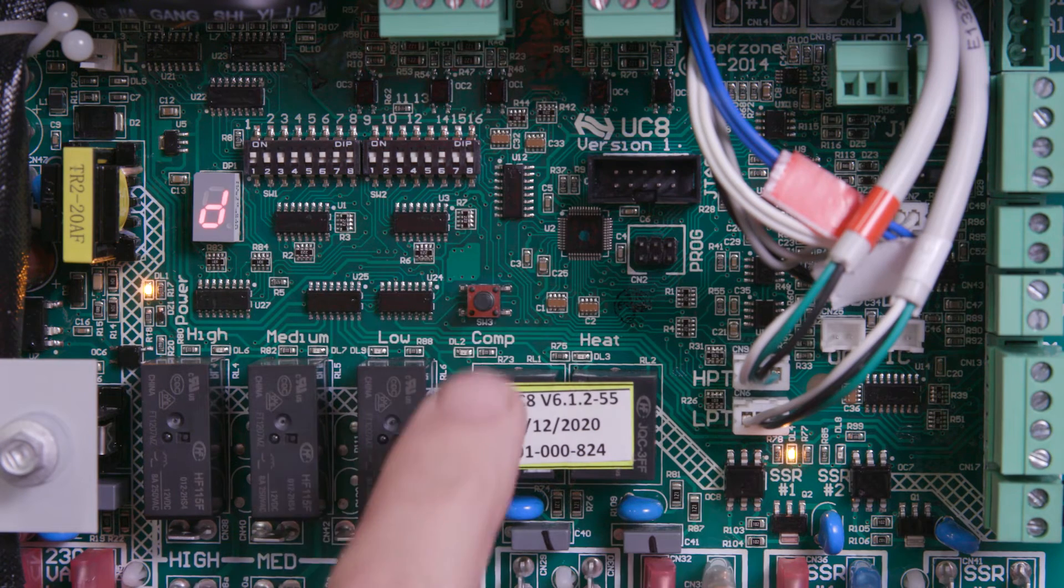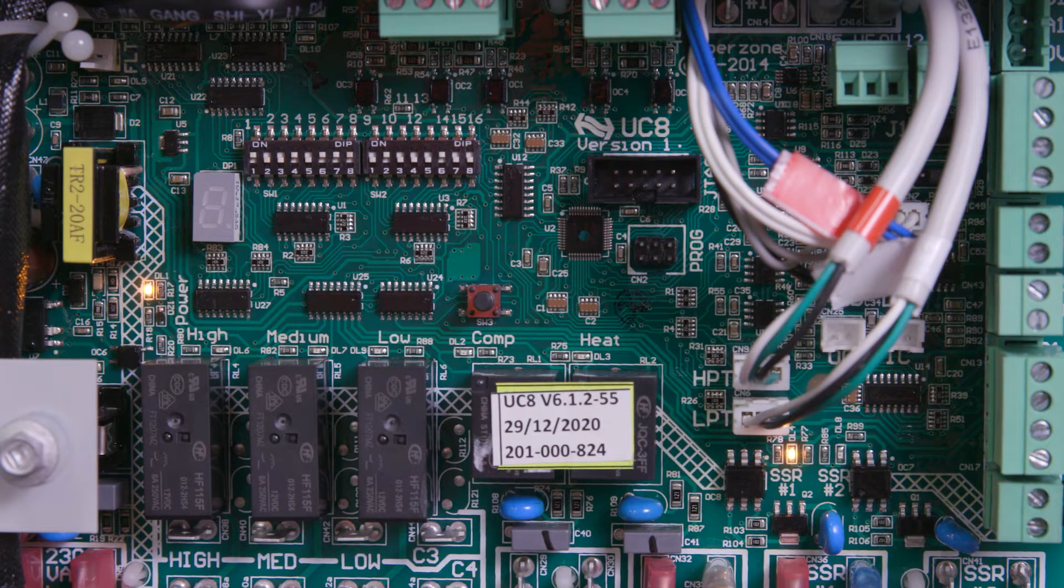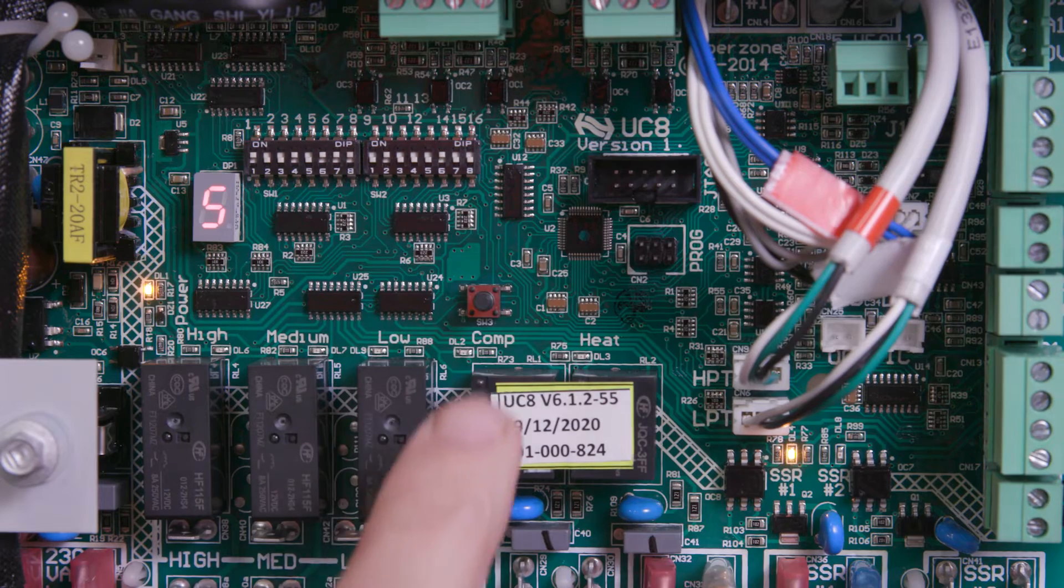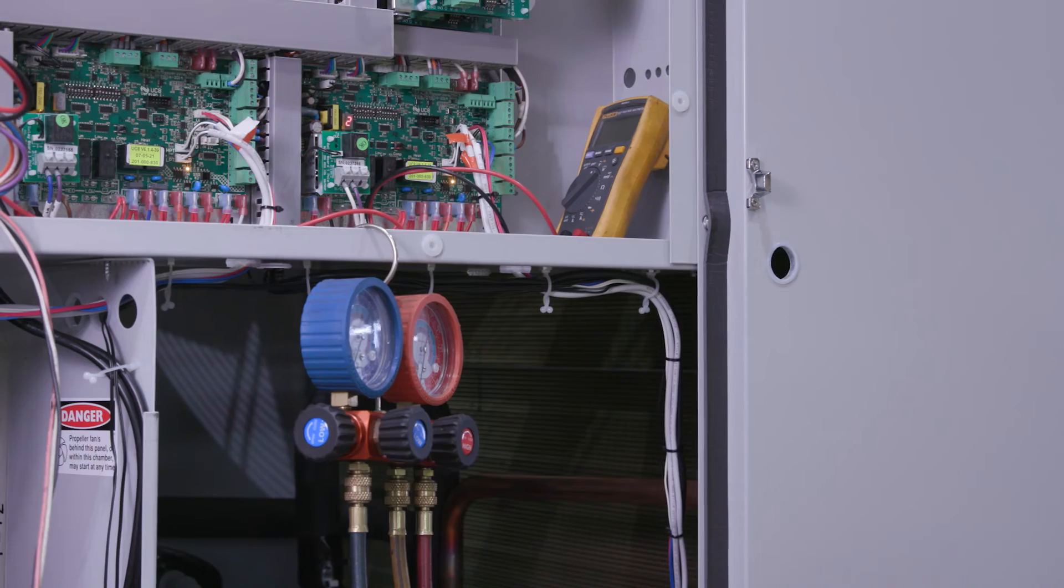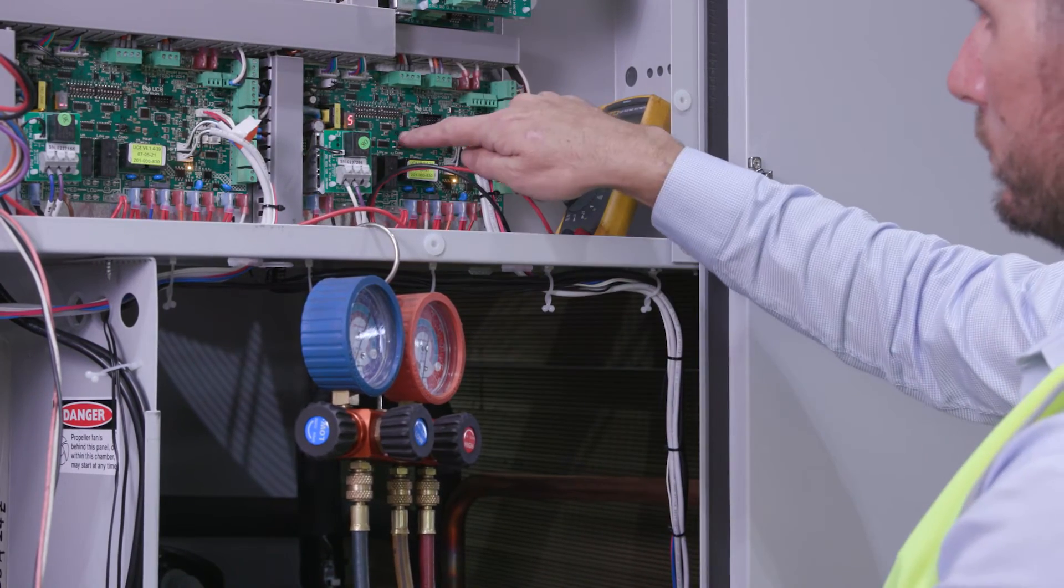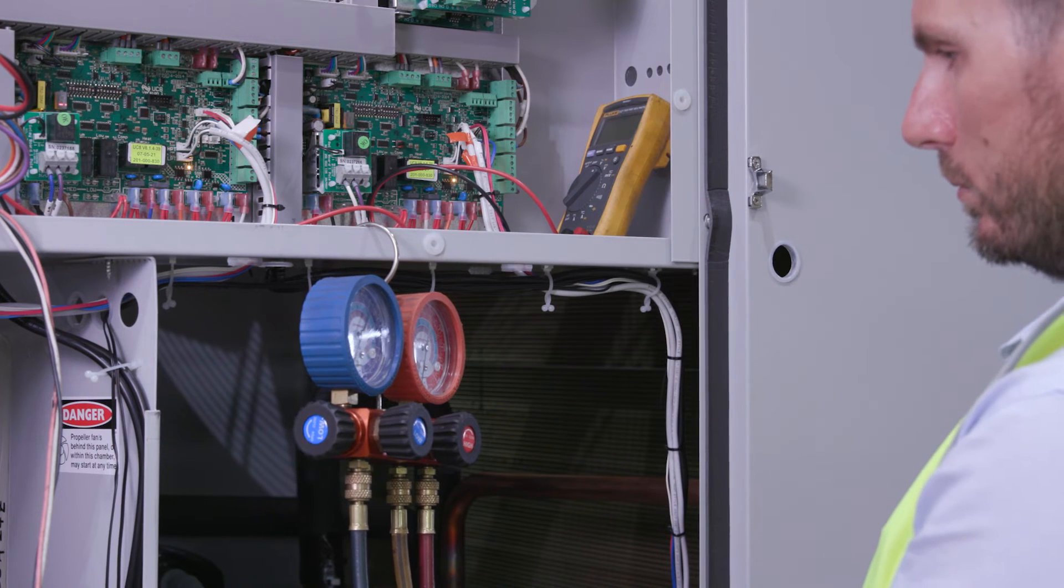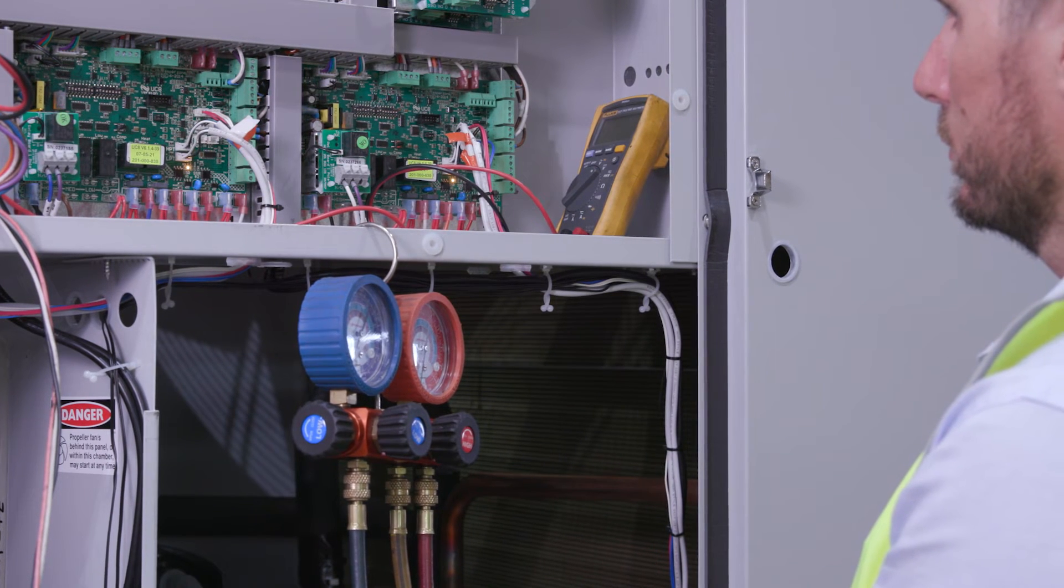Check the discharge and suction sensors calibration compared to the UC8 display with the unit operating. Check the accuracy of transducers by comparing high and low side pressure readings to those read on the UC8 display.